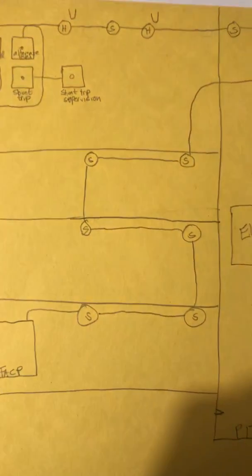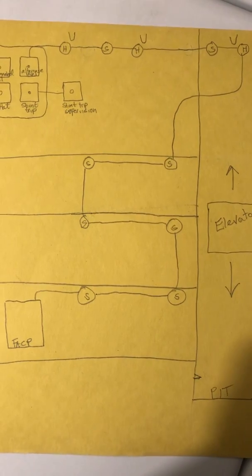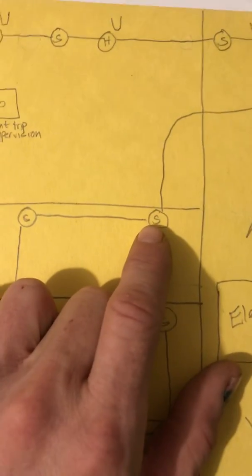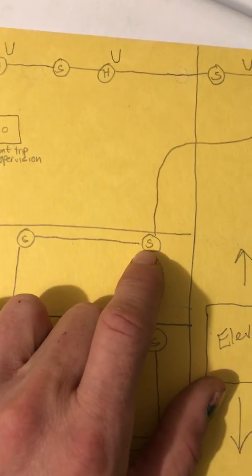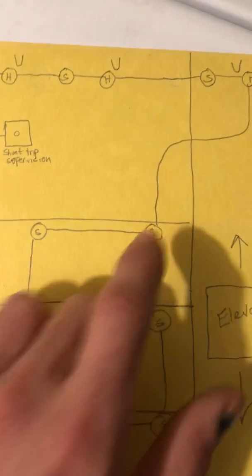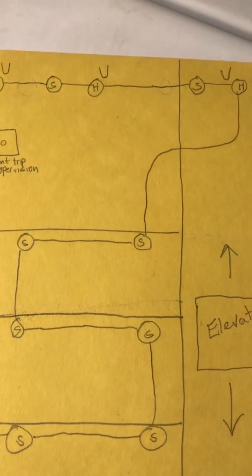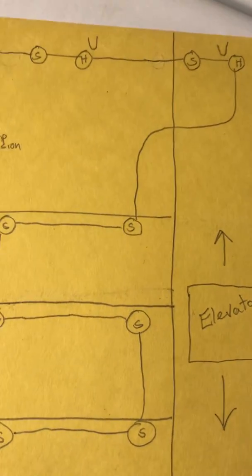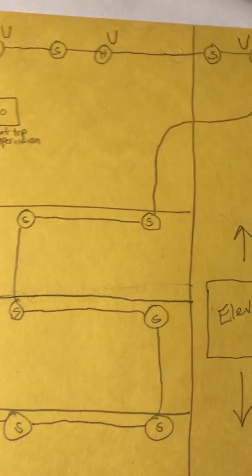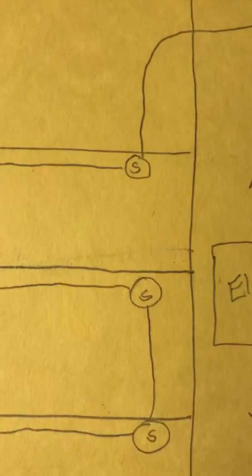Coming down on your different floors, you're going to have smoke detectors in your elevator lobbies, and you want to keep these smoke detectors within 21 feet of the center line of the elevator doors. That's the code right there.